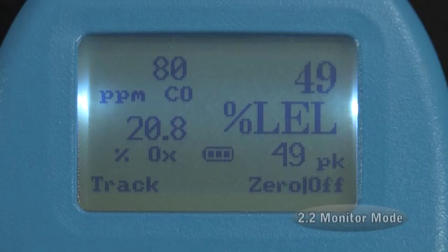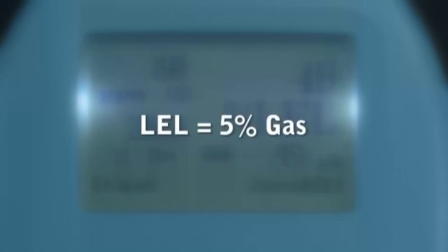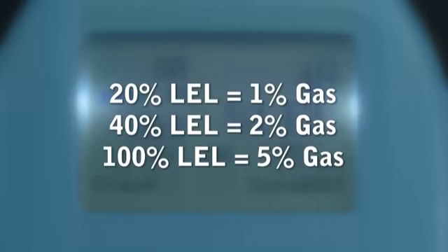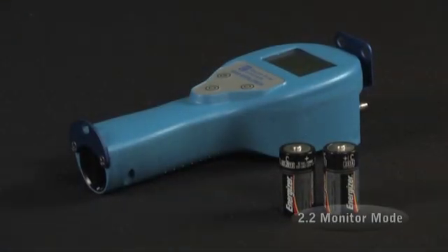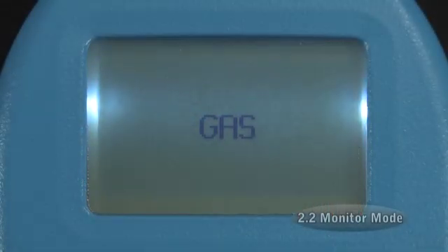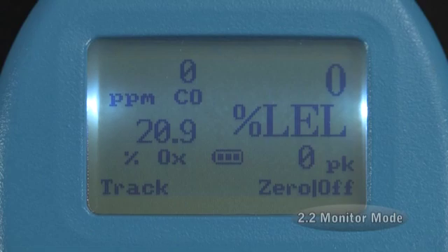The concentration of natural gas can be expressed either as percent gas or as percent LEL, which stands for lower explosive limit. For methane, the lower explosive limit is 5% gas. Thus, 20% LEL is 1% gas, 40% LEL is 2% gas, and so on to 100% LEL, which is 5% gas. Some companies prefer to keep all measurements in the same units, namely percent gas, while others prefer to use the percent LEL scale. Your Explorer is configured to conform to your company's policy.